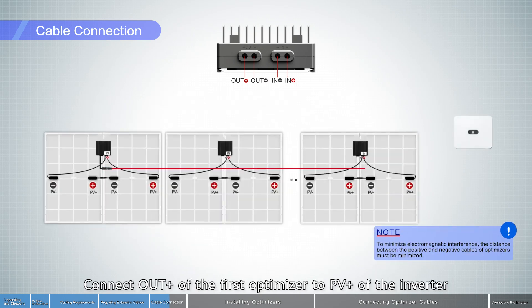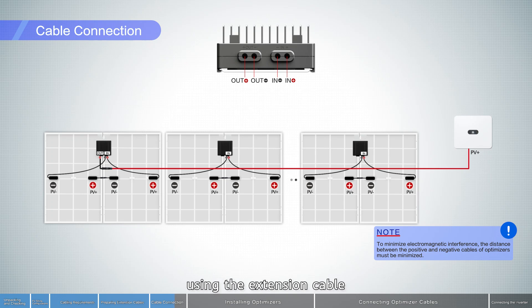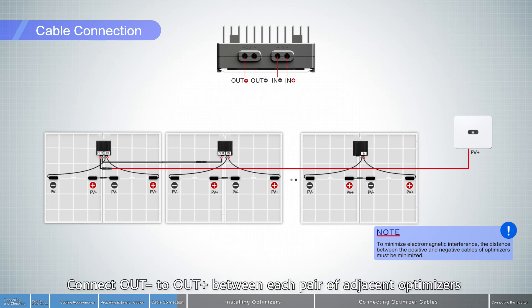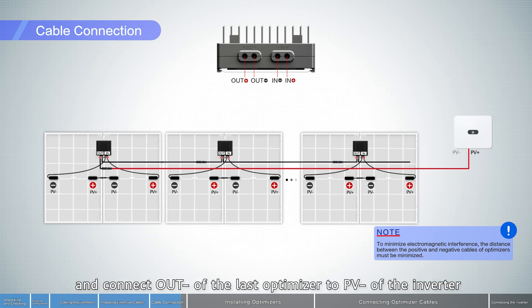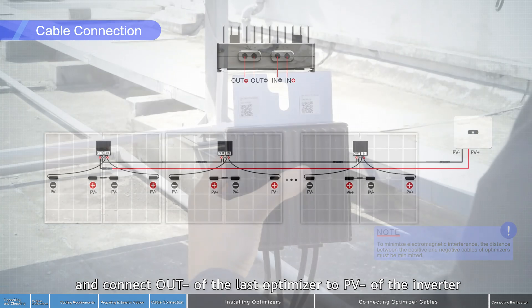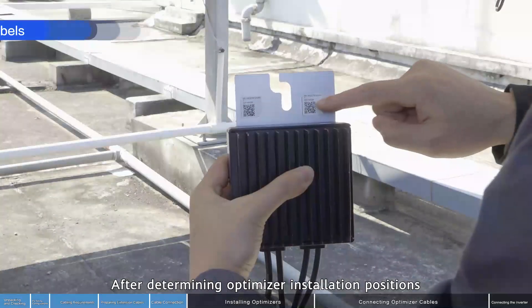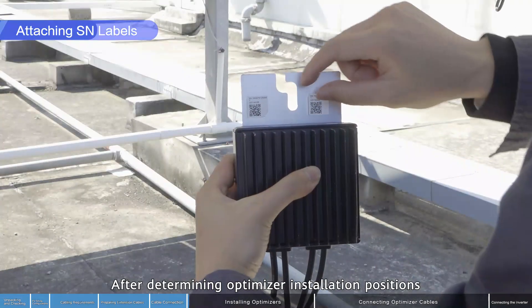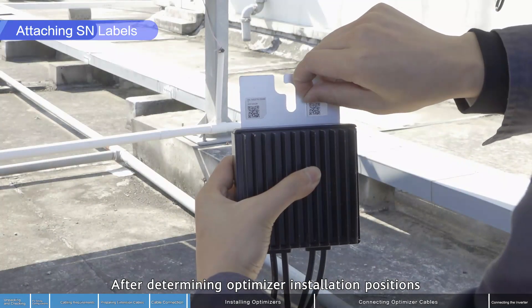Connect out positive of the first optimizer to PV positive of the inverter using the extension cable. Connect out negative to out positive between each pair of adjacent optimizers, and connect out negative of the last optimizer to PV negative of the inverter.